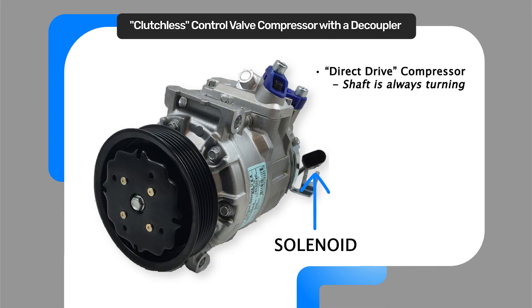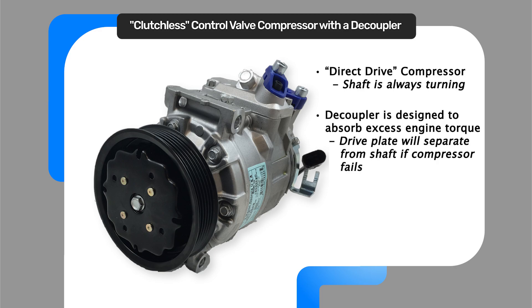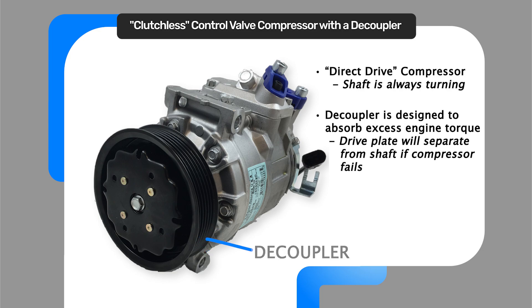This control valve compressor can also be referred to as a direct drive compressor. The motor is directly attached to the compressor crankshaft, keeping it in motion. The decoupler is essentially a protection feature — if the compressor fails internally, the drive plate will separate from the shaft. It is important to verify that the shaft is turning during diagnosis.